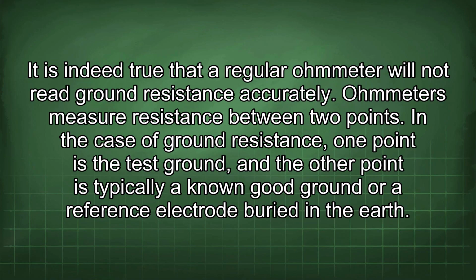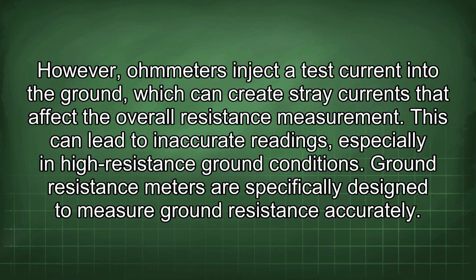It is indeed true that a regular ohmmeter will not read ground resistance accurately. Ohmmeters measure resistance between 2 points. In the case of ground resistance, one point is the test ground, and the other point is typically a known good ground or a reference electrode buried in the earth. However, ohmmeters inject a test current into the ground, which can create stray currents that affect the overall resistance measurement. This can lead to inaccurate readings, especially in high-resistance ground conditions.